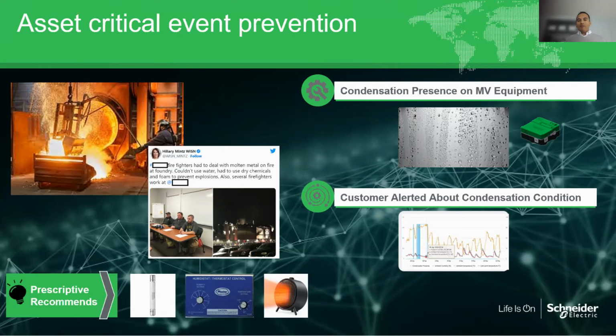By means of sensing technology and analytics, we were able to detect that at certain points during the day and certain times during the year, they were having condensation presence inside the equipment. Outside it was too hot or too cold, and inside the equipment it was probably too hot. So you have that rainforest effect, the same thing you get in your car in the mornings when it was very cold during the night and then all of a sudden it starts warming up in the morning.